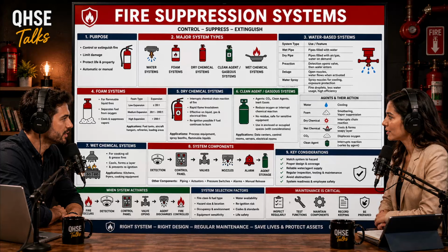Which ties perfectly back into another core process safety management concept, management of change, or MOC. Yes, MOC is arguably one of the most critical functions of a safety engineer. Facilities are not static. Give me a practical example of how MOC applies to fire suppression. Let's say your company takes a storage room that has been storing cardboard boxes for years and decides to convert it into a chemical mixing room for highly flammable solvents. You're fundamentally changing the chemistry of the fuel load. Exactly. You're changing from a Class A hazard to a severe Class B hazard.